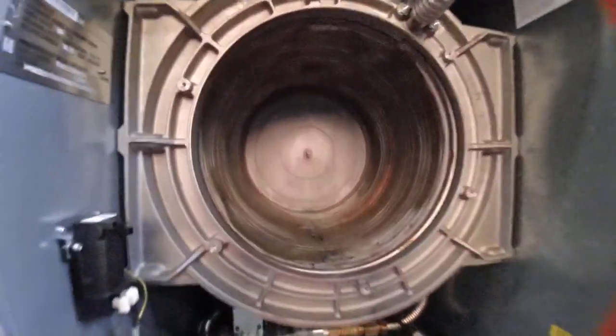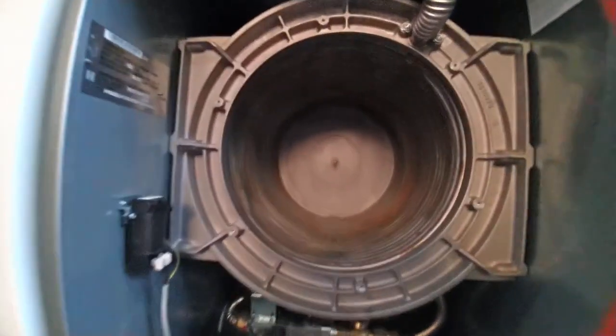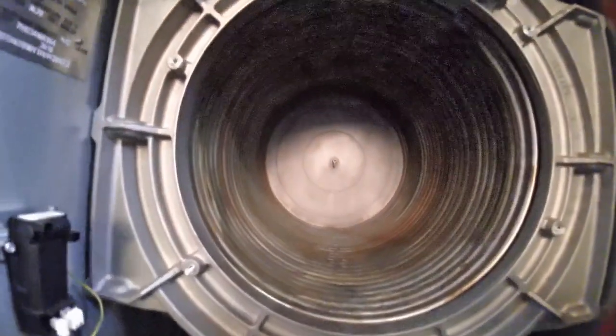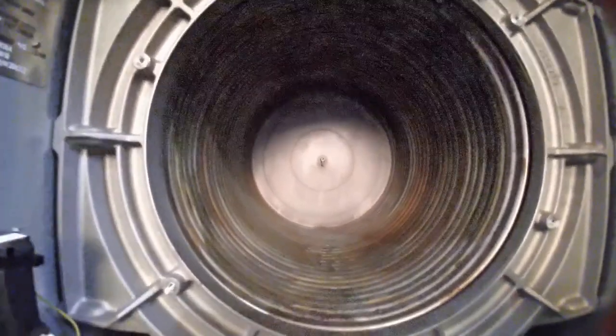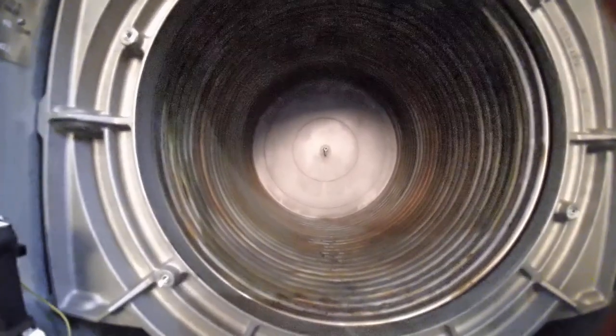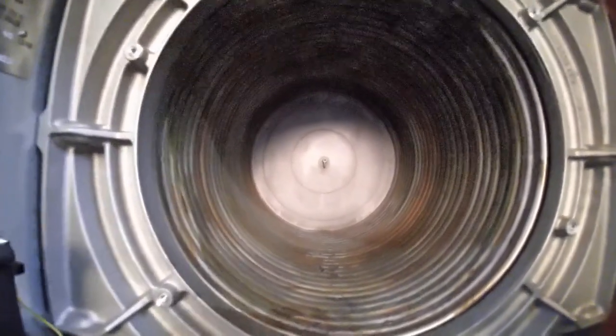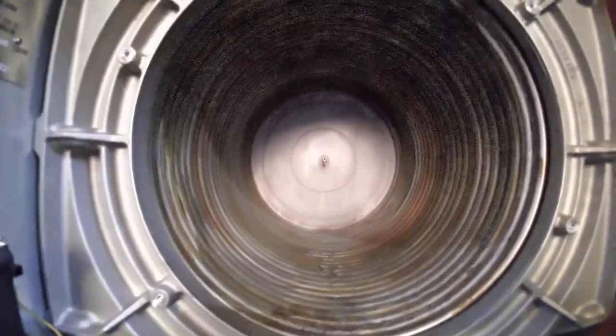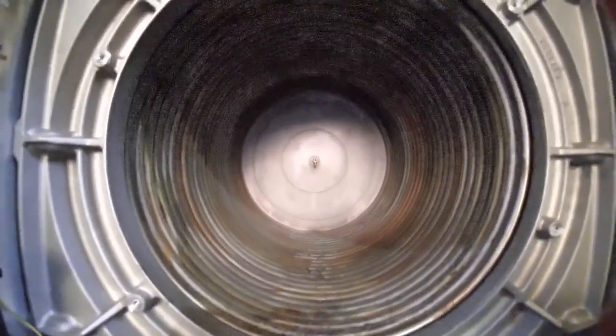We've also taken out the rear refractory in preparation to clean this heat exchanger. We don't want to get that wet when we're spraying water in here to clean this down after we've brushed it all out. Now that we've cleaned down between the tubes with the proper cleaning brush supplied by the manufacturer, we're just going to gently wash it with some hot water. Most manufacturers supply some type of cleaning tool, and it's important to always use what the manufacturer supplies and recommends.